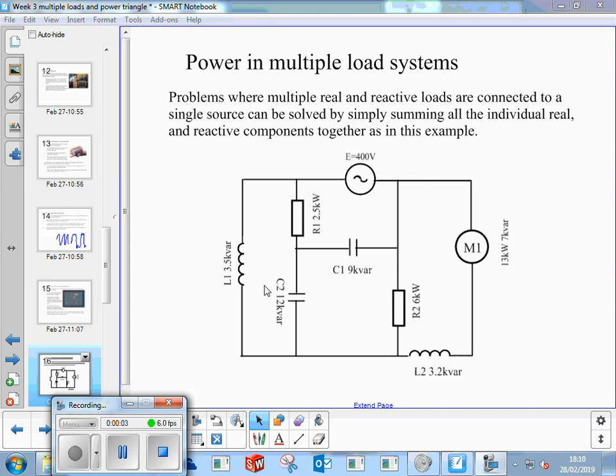Power in multiple load systems. Problems where multiple real and reactive loads are connected to a single source, like at a distribution point in a switchroom. You've got a main incomer that's got several loads connected to it. You can solve these by simply summing up all the individual real, reactive, and components together, and then calculate an overall apparent power as well.